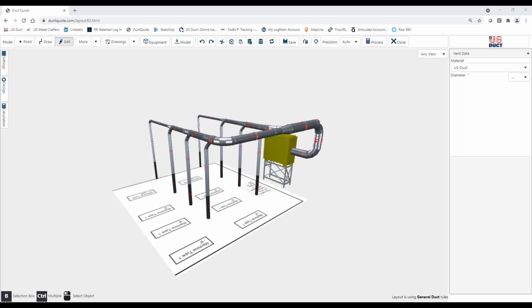Welcome back to the views here. We're going to talk about the basics of balancing your system. Now, when you're balancing an industrial ventilation system, you must determine the needed flow volume for each pickup point or entry point.